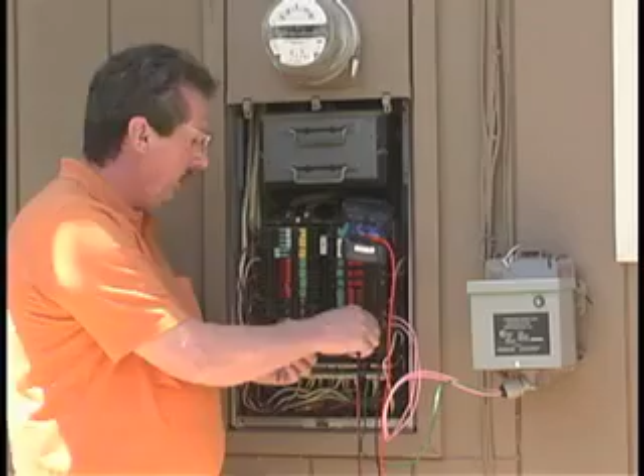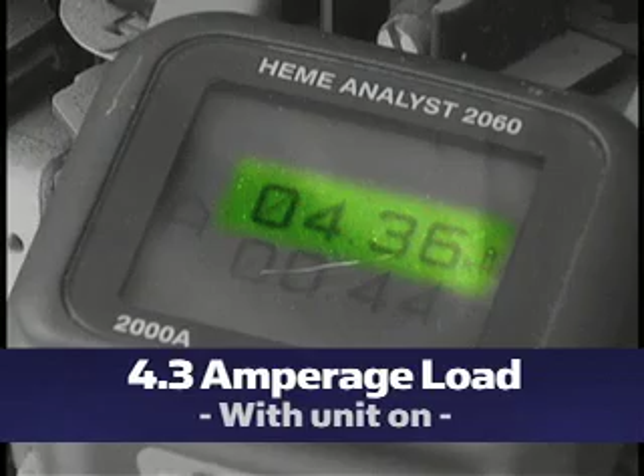Here we have a temporary installation of a PU 1200 on a private residence. By testing it with this meter on the amperage load with small appliances on in the home, the current amperage reading is 8.3. With the unit on, the amperage rating is 4.3. We've cut the amperage in half.